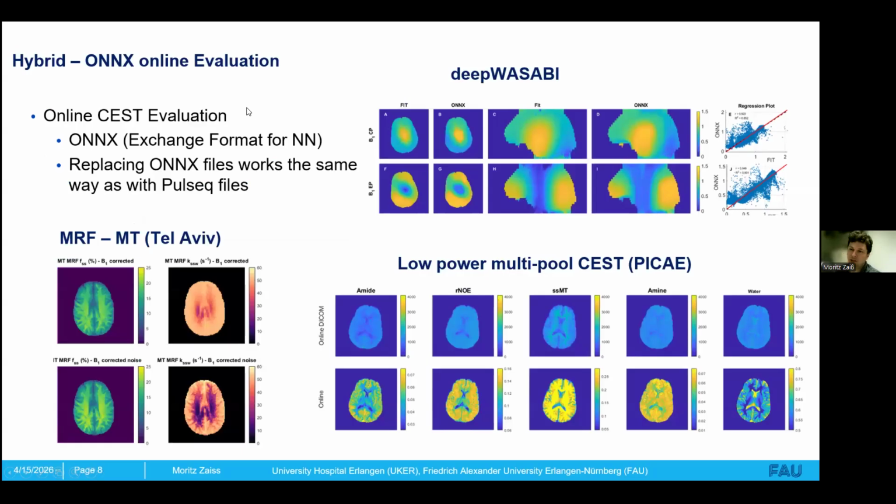If you have now this PTX preparation, you can also do WASABI for different modes. So for example, here's the circular polarized mode or an elliptical polarized mode, and you can measure the B1 and B0 maps of these. And these are the modes that we mix at 7 Tesla for this MIMOSA saturation, and then you get a quite homogeneous saturation also at 7 Tesla.